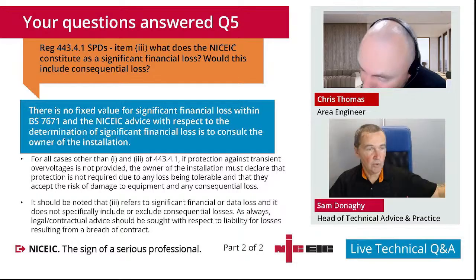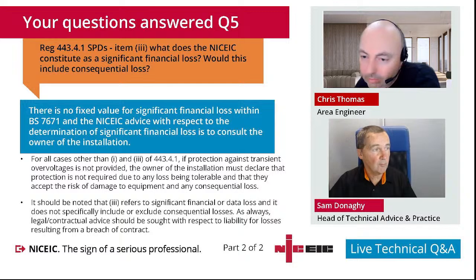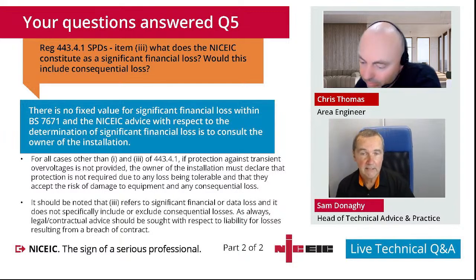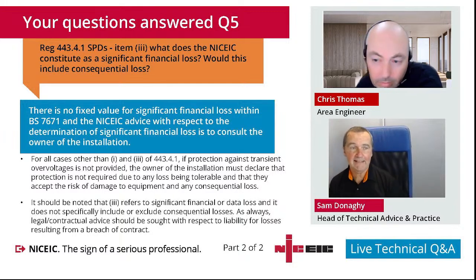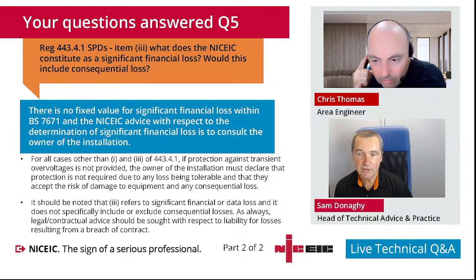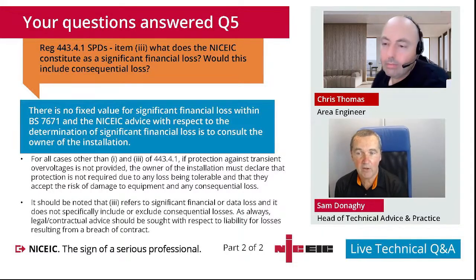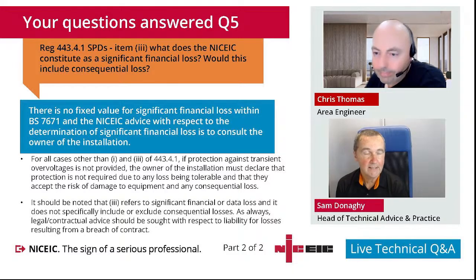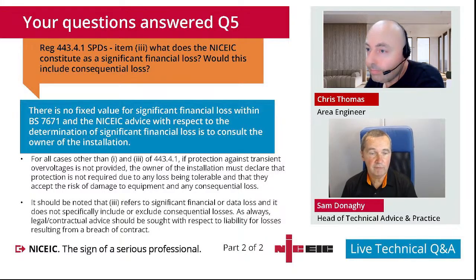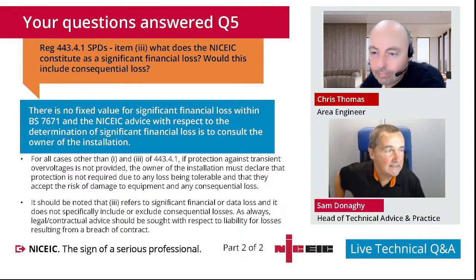considered, but it's absolutely right, is volt drop. So often we use a larger cable than we really need where we've got issues of volt drop. So if we have got a very long circuit, so that therefore we've increased our volt drop on that basis, then we might up the cable size just to reduce that volt drop. So that's a really good point that one of the engineers has made. So that might be the reason.